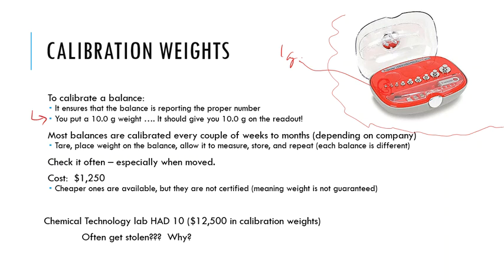They come in different sizes: 1 gram, 2 gram, 5 gram, 10 gram, 100 gram, 50 gram. They go all the way down to 1 milligram sometimes, which is just like a little bitty fleck of metal that you would put onto an analytical balance. Most of the time, these checks with the calibration weights are done at least every couple of weeks. And then sometimes in heavily regulated laboratories, these calibration weight sets could be used daily.